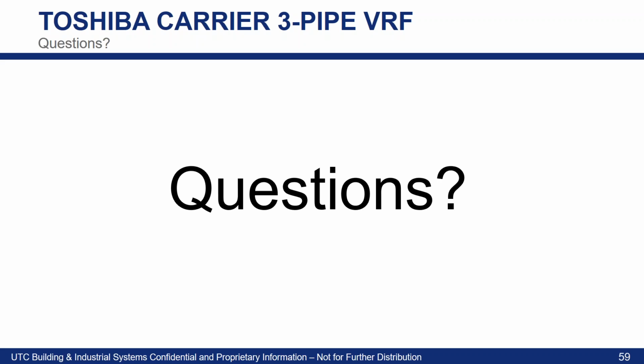I really want to know what else we're talking about, because we're not just talking about that single zone that's going to need low ambient cooling. When we're dealing with VRF, we're going to have a much larger system. So I might very well tell you to isolate that single zone with, let's say, a ductless system, 1-to-1. That would probably be the best option, but I do understand that there are situations where you want that cooling and heating to be all on one system. But yeah, more application specific there.